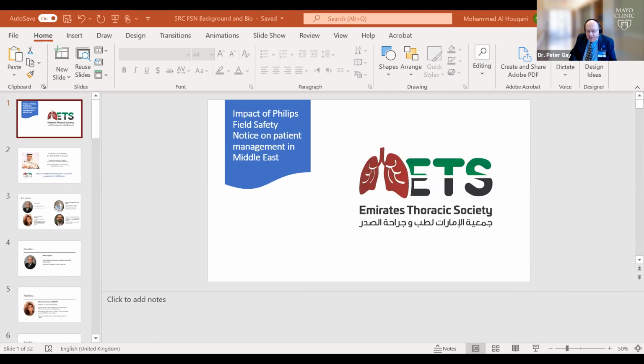But what I will tell you is that the most toxic one in terms of carcinogenicity is the dimethyldiazine, and that seems to come off quickly and disappear. So there are some agents that do disappear quickly. In terms of the others, there are unpronounceable phenol compounds that seem to come off in a much more continuous and slow fashion. So the older machine still may give off the phenols if exposed to the right environment. If you have an older machine that was kept on a shelf in a cool room and now you move it to a warm environment, now you've got a new situation where that foam starts to degrade. It could be variable for any machine, any age. I hope that's not more confusing than helpful.